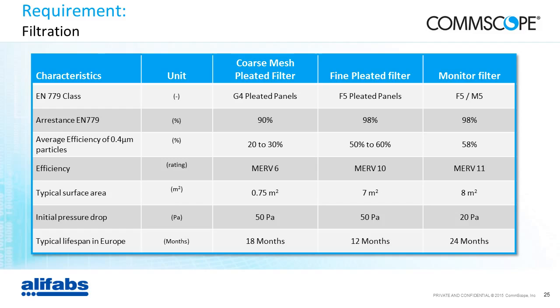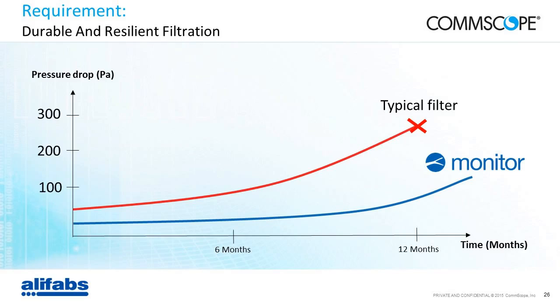So how does it compare with a typical G4? Well, we've put a curve together to just give you an idea. The monitor filter starts at 20 pascals and increases slowly, and it takes quite a while to reach the point when it's actually affecting the performance of the system. Like I said, 24 months on average. Whereas typically a G4 filter will start at 50 pascals and will reach 250 pascals over a period of 12 months. That is on average for a G4 filter. So that gives you an idea of what our system can deliver.